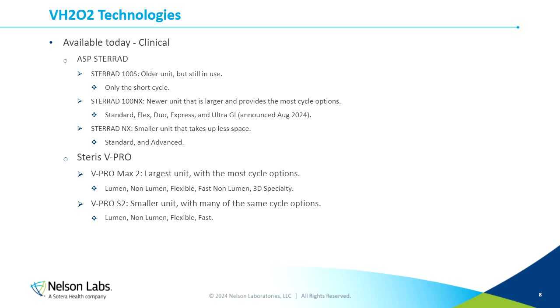So the next is one of the largest units offered by ASP, which is the STERRAD 100NX. It is a newer unit compared to the 100S, and it is a very large unit. Physically, it is large and will take up some space in order to be used, but it does have the most cycle options. So it offers quite a bit of flexibility in finding the cycle that your product will fit into and be validated to. Its normal cycles are the standard cycle, the flex, the duo, the express, and one that was just recently announced this month, the Ultra GI cycle as well. So it is a newer unit that is gaining new cycles, and it offers quite a few different cycles for you to choose from.